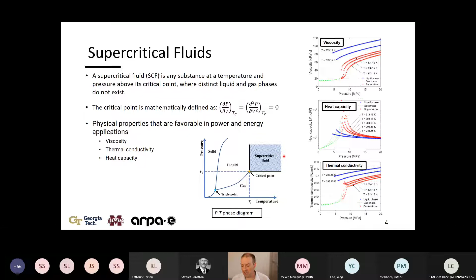But then there's actually one more option, and this is the supercritical region, which is a region that is accessible above a certain critical pressure and critical temperature. So the fluids in that region, they have partial compressibility and very low viscosity, but they're extremely dense, which helps with thermal needs, but also with arc quenching needs. And it has actually a very high dielectric strength.